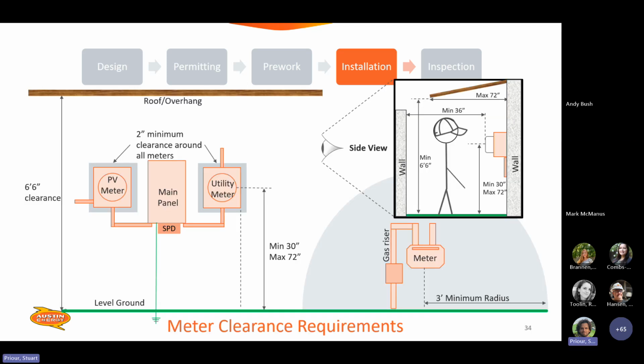And as far as meter location goes, like I said, you need 2 inches around all cans. You need at least 6.5 feet of overhead clearance at the location of the meters. 30 inches minimum, 72 inches maximum to the center of the can, and a 3-foot radial clearance around gas meters, gas regulators.